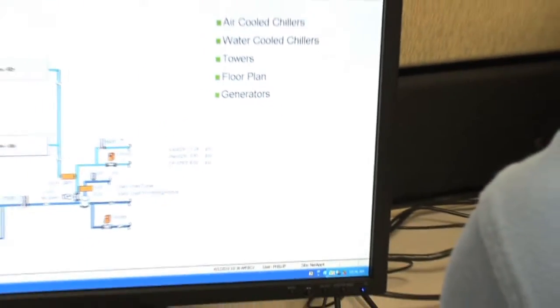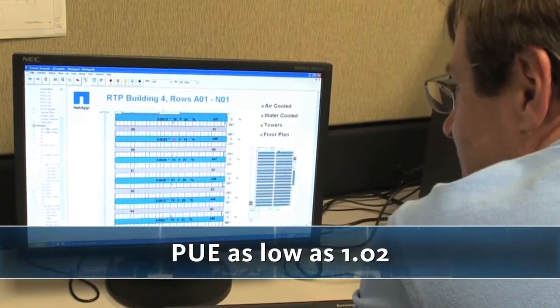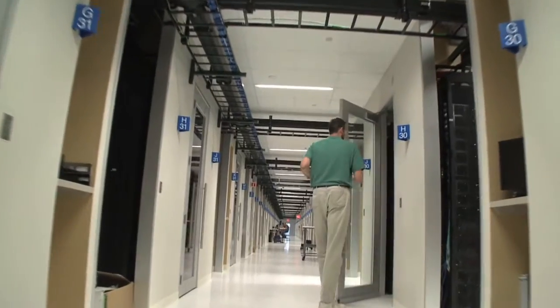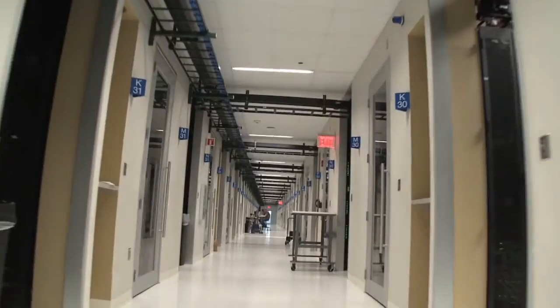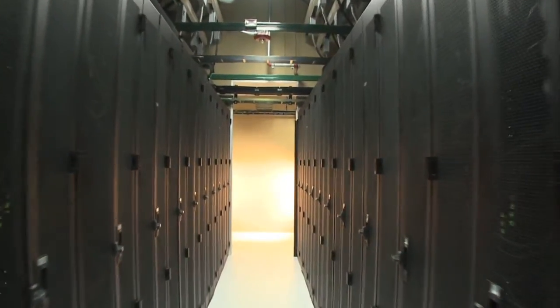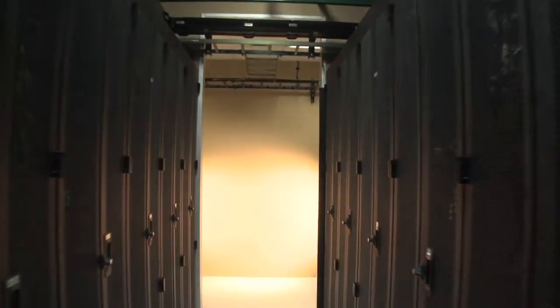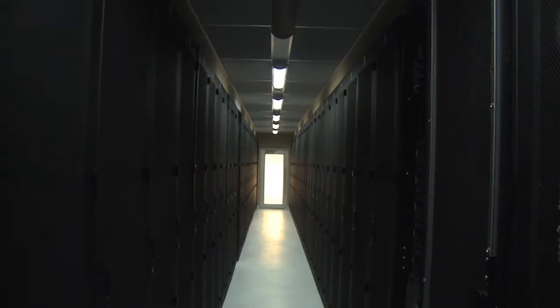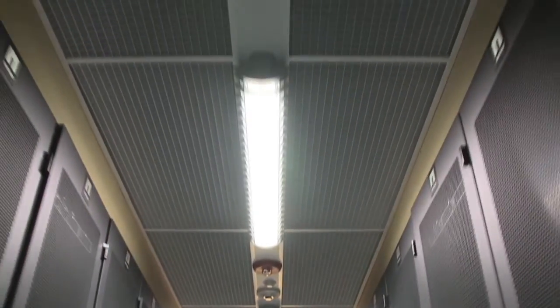When we are operating in the free cooling mode, the PUE can be as low as 1.02. In the corporate IT racks, doors are installed on both the hot aisles and cold rooms to provide a more secure environment that is strictly controlled. We leave them off unless required for physical security to allow for free movement around the data center. As we walk into one of the pressure-controlled cold rooms, you can see the doors on both ends as well as a lowered ceiling that seals the top of the rows. In addition, blanking panels are deployed in the racks where no IT kits are installed to prevent airflow between the hot aisle and cold room.